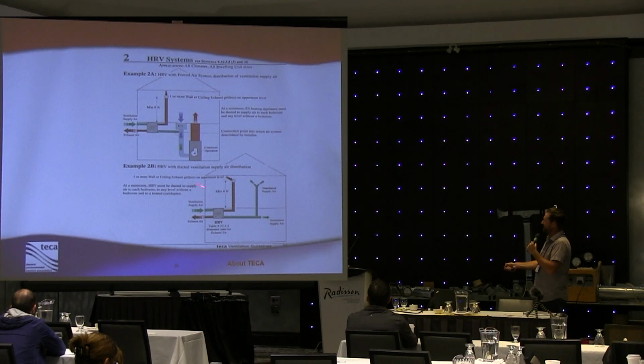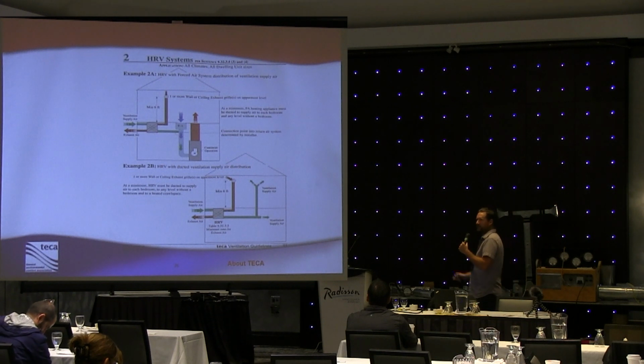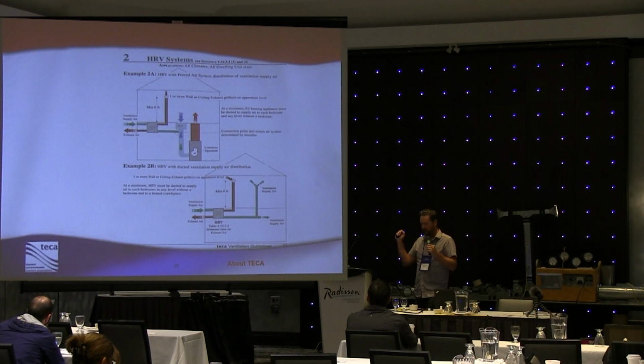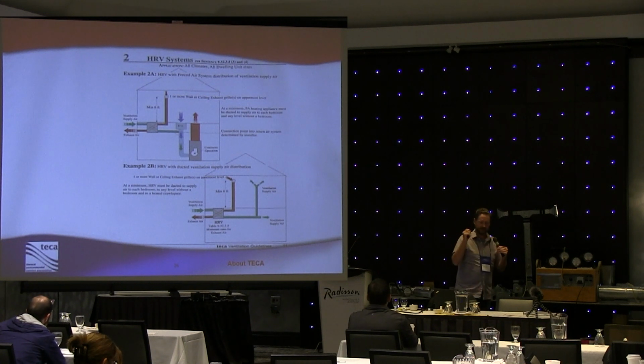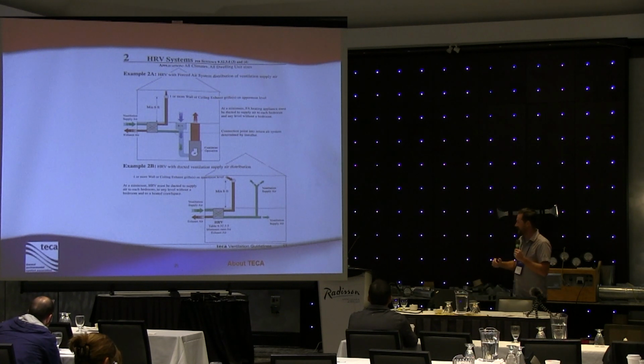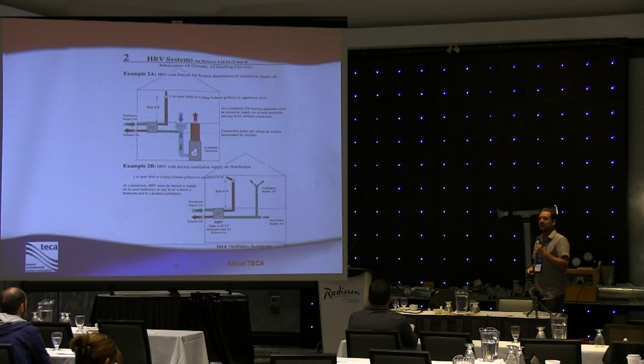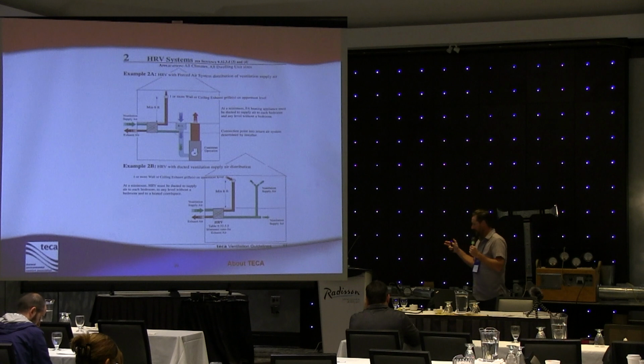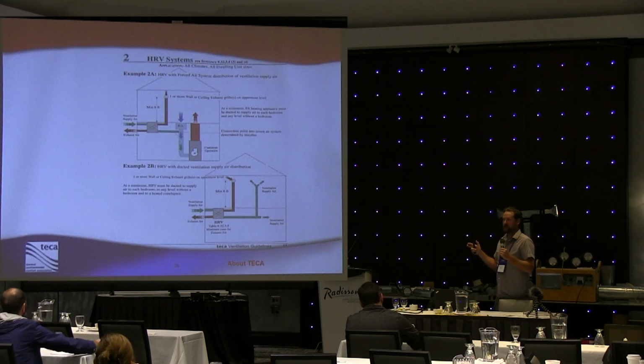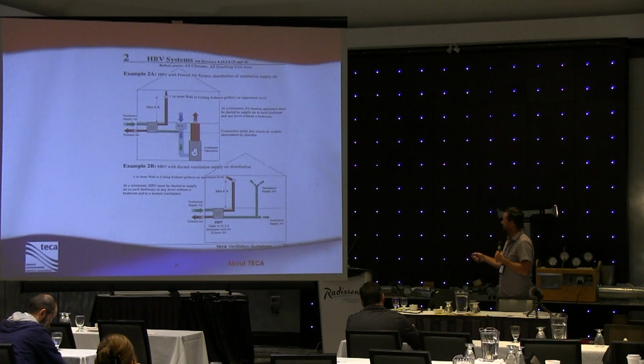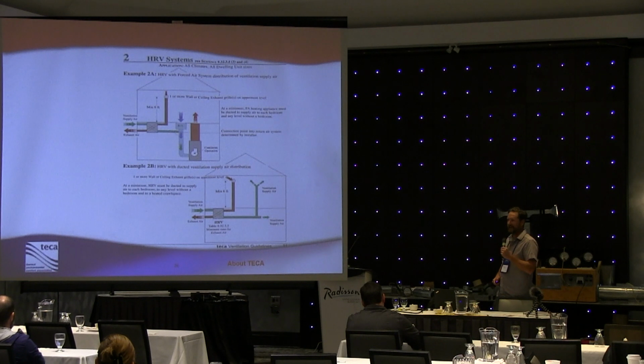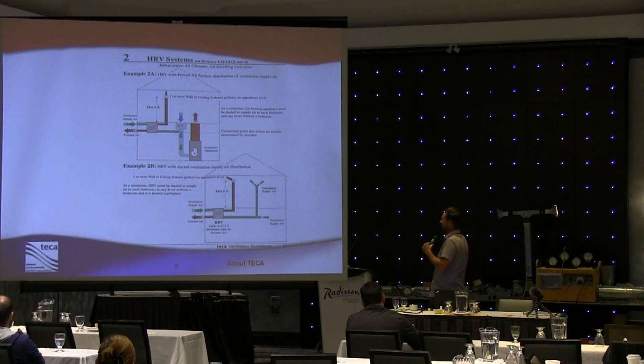Now if you look down here, I've got an HRV with ducted ventilation. So this is an HRV that's standalone, and we're going to see these more and more often in homes that have an alternate form of heating, whether it's electric baseboard, hot water radiant heat, heat pumps, things like that, where there isn't a distributed heated air system. It's going to be some other type of heating system installed in the building. And these HRV systems, standalone like this, again, very, very good for providing nice fresh air and to minimize that energy impact of exhausting conditioned air to the outside.